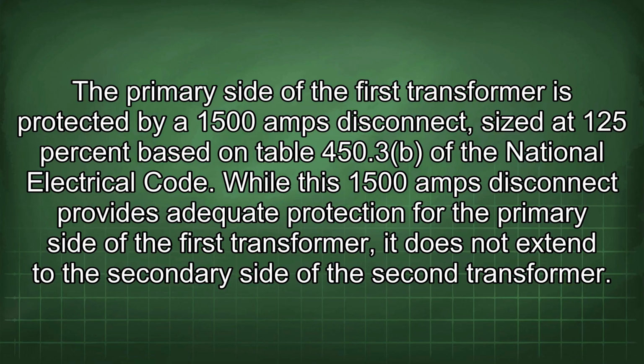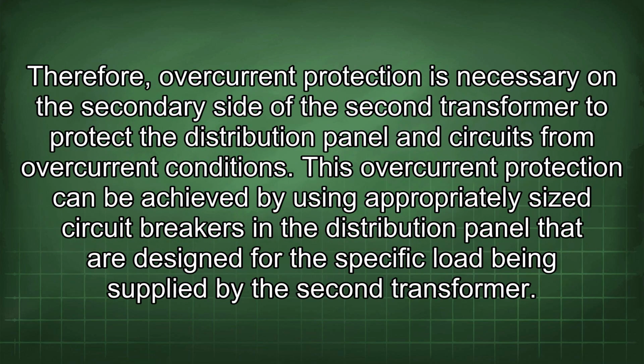125% based on Table 450.3 of the National Electrical Code. While this 1500 amps disconnect provides adequate protection for the primary side of the first transformer, it does not extend to the secondary side of the second transformer.